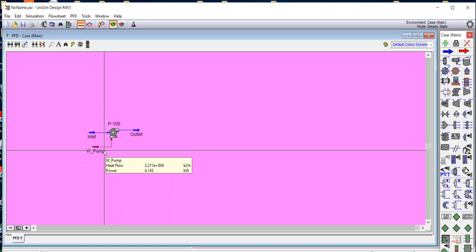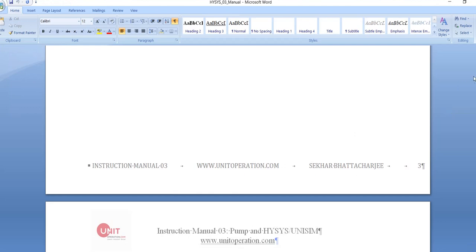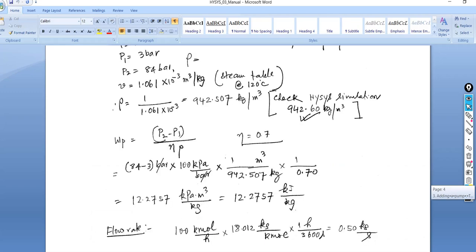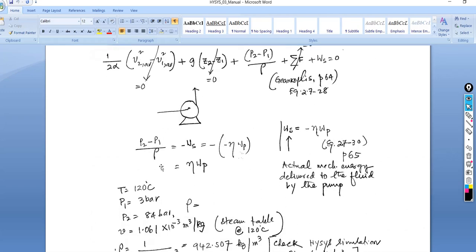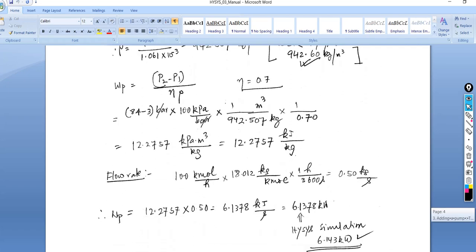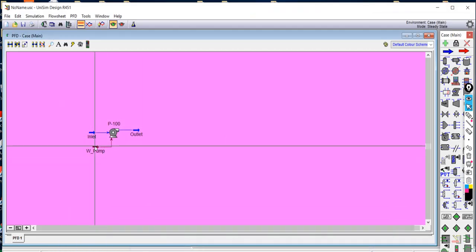Hovering over the W_pump energy stream, the power requirement is 6.143 kilowatts. As a verification, solving Bernoulli's equation with T1 = 120 degrees Celsius, P1 = 3 bar, and P2 = 84 bar gives a theoretical result of approximately 6.1378 kilowatts, which is very close to the simulated value of 6.143 kilowatts.